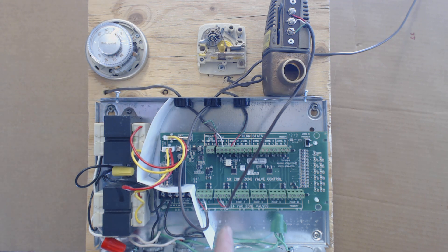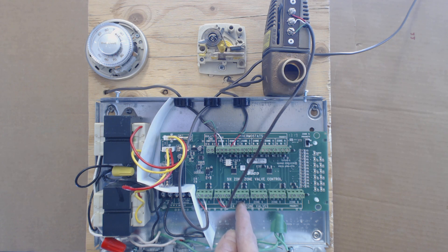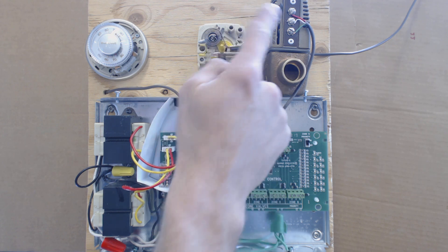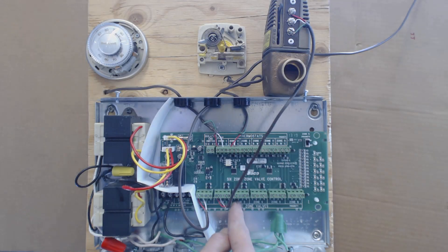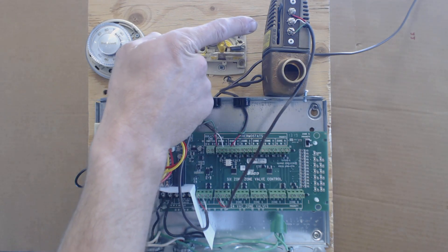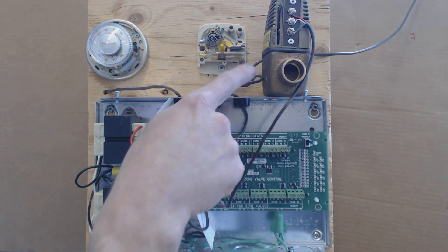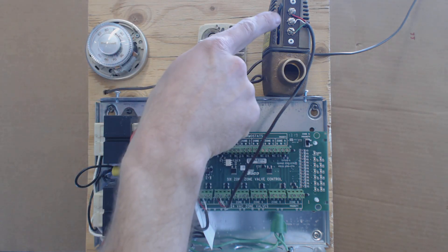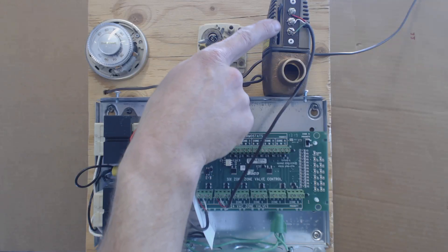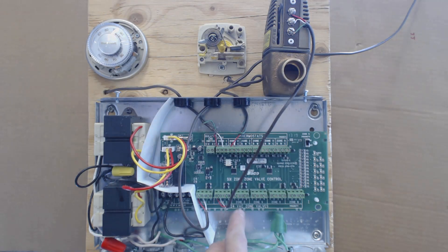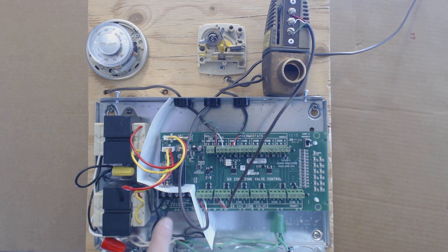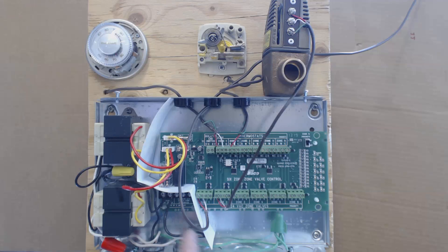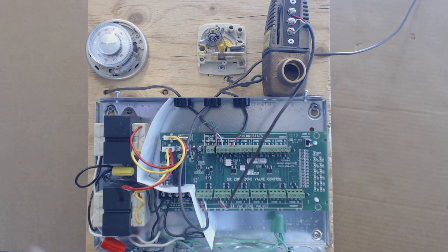So, TACO zone valves, just to go over it again, let's go to zone three. One is power, two is common, and three is the end switch. When you power it with one, it powers up here, it comes back through the common, and that completes the circuit. You're heating the element up in here. It's pressing on the valve body. Once it opens completely, two, which is common, and three, which is the end switch, they touch. Once this board senses continuity between two and three, that's when it turns the pump end switch on and turns the circulating pump on and allows you to pump the water. So that's basically how it works.